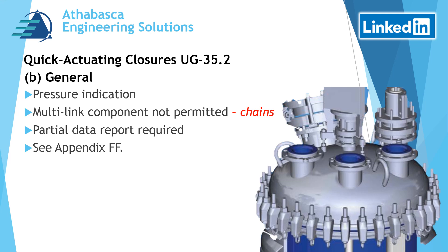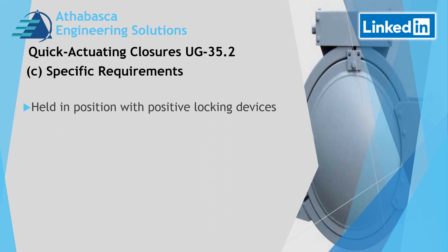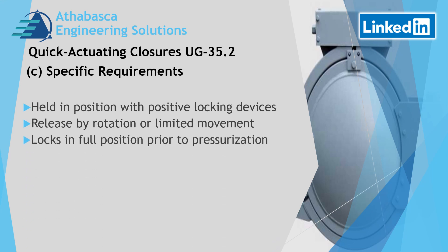ASME recognizes it cannot cover every type of design in the universe, so it tries to give the designer some fundamental rules to follow. Other specific requirements include: the closure must be held in position with positive locking devices; release by rotation or limited movement is a required design feature; and it must lock in the full position prior to pressurization.